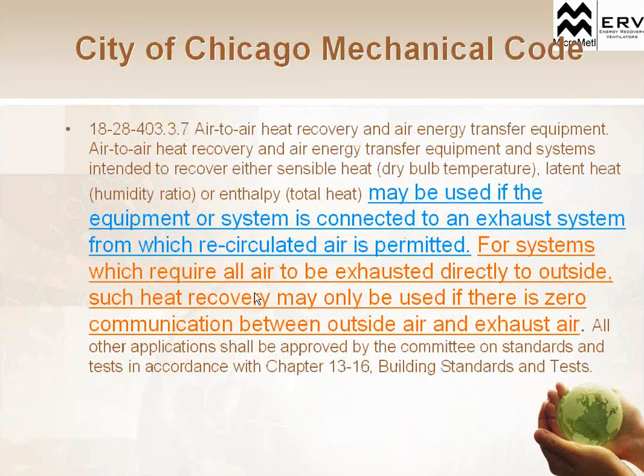They've also finally talked about toilet exhaust, which is specific, and I'll go right to the City of Chicago code, because the City of Chicago code is very specific on toilet exhaust. This applies to you. Toilet exhaust is not able to be used in recovery applications. You can't use toilet exhaust in a wheel recovery application. I'll kind of comb through some of this code lingo. But you can use a fixed plate heat exchanger in the City of Chicago because of the transfer ratio.